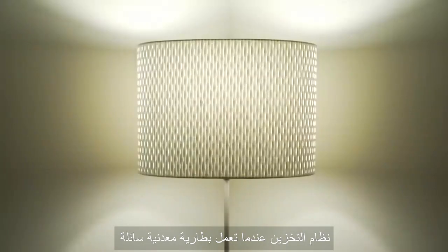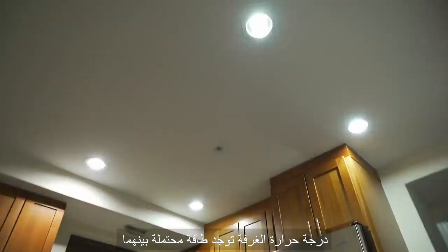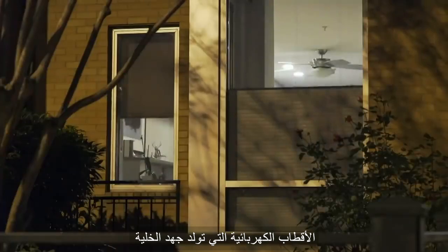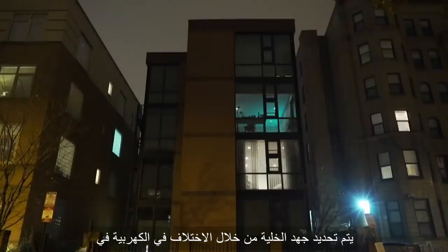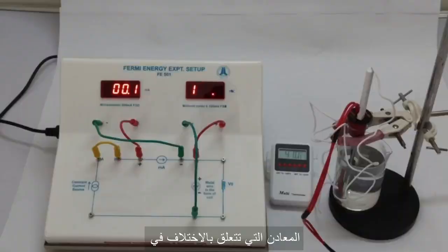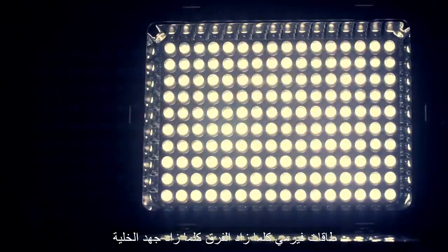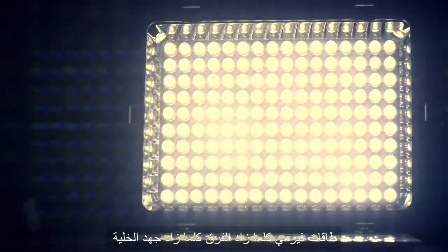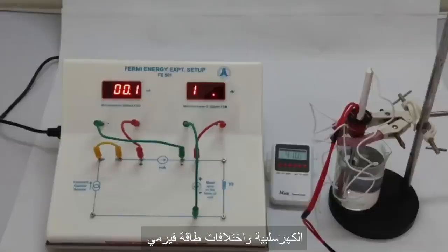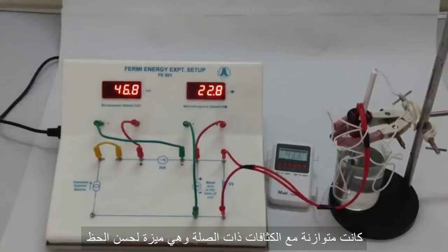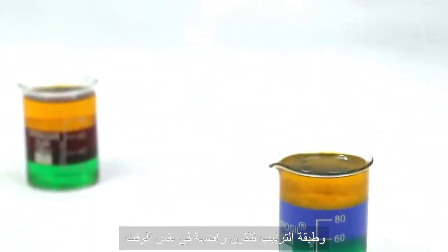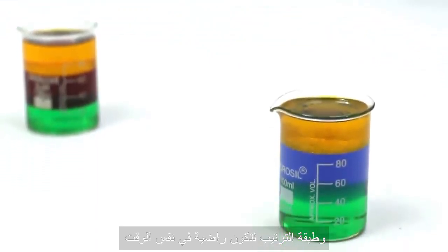When a liquid metal battery operates, there exists potential energy between the electrodes, which creates a cell voltage. The cell voltage is determined by the difference in electronegativity of the metals, which relates to the difference in their Fermi energies. The larger the difference, the greater the cell voltage. These electronegativity and Fermi energy differences were paralleled by the respective densities, a feature which fortunately enabled the requirement for liquid density differences and layer ordering to be concurrently satisfied.